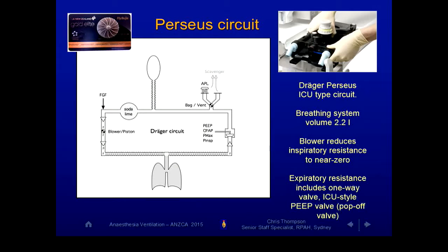There's one other small detail: there's a very high resolution screen with lots of accurate waveforms, most important being flow. On our old machines we had CO2, but CO2 isn't very important really, it's a secondary consequence of adequate ventilation. It was just the only thing we could measure for 20 or 30 years. Now we've got really high quality flow curves built into the machine. As soon as you see exhaled flow, you know the CO2 is going to be okay, you know gas is coming out.